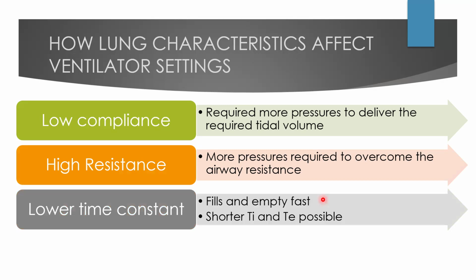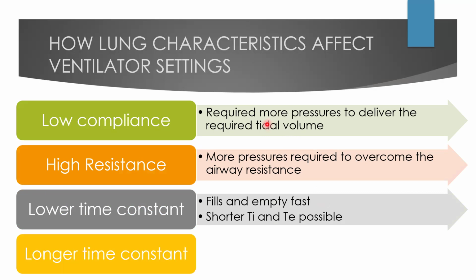When we have a lower time constant, the lung unit fills and empties fast. Shorter TI and TE will be possible, and with a longer time constant, we need to set a longer TI and TE.